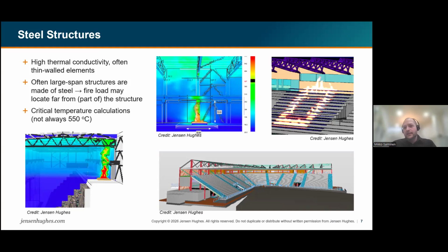As you probably know, steel and other metals have high thermal conductivity, and they are often quite thin-walled elements, so as a result they heat quite fast. As I mentioned, in something like 15 minutes they might already reach 500 degrees average temperature in the cross section. But on the other hand, steel structures are widely used in large-scale buildings with large spans, and the steel structure may be located quite high from the ground. So the fire load, especially where there is low fire load in the building, may be located far from the structure, which opens up some possibilities for structural fire engineering.